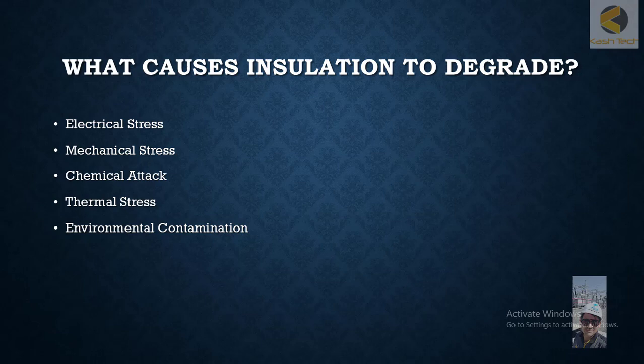The heating source could also be from outside — from another cable, or maybe from the sun. In that case the insulation will also get heated. Another case could be that the cable selected is of a low rating but the load is more than that, so this cable will be subject to more heating and the insulation will be damaged quickly.